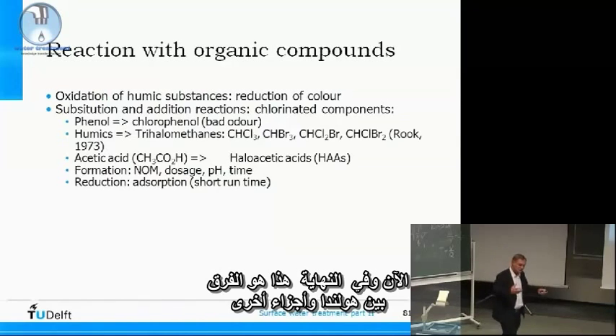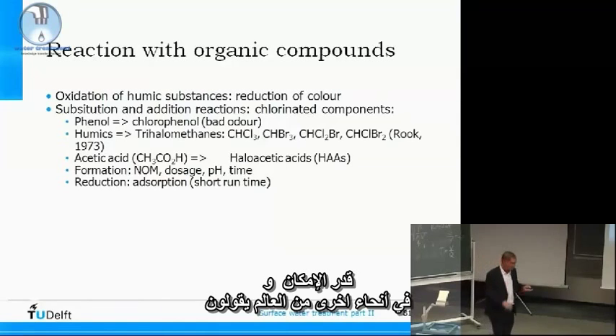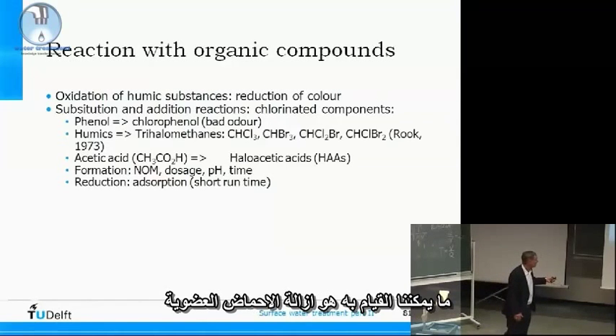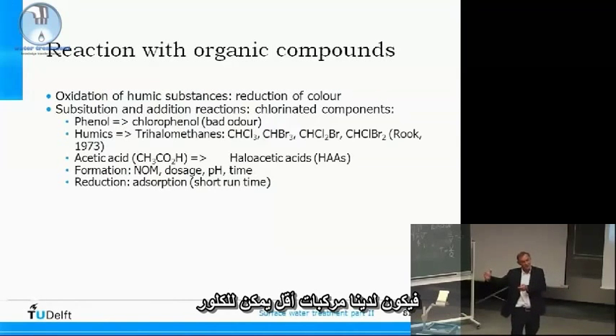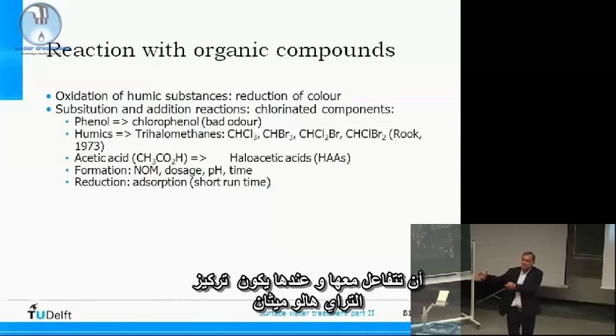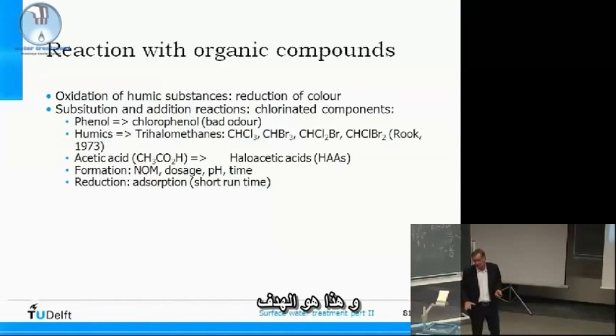This is the difference between the Netherlands and other parts of the world. In the Netherlands, we avoid chlorination as much as possible. In other parts of the world, the approach is to remove the humic acids and organic material before chlorination, so there are fewer compounds for chlorine to react with, and the concentrations of trihalomethanes and haloacetic acids are reduced. Another approach is to dose as little chlorine as possible.